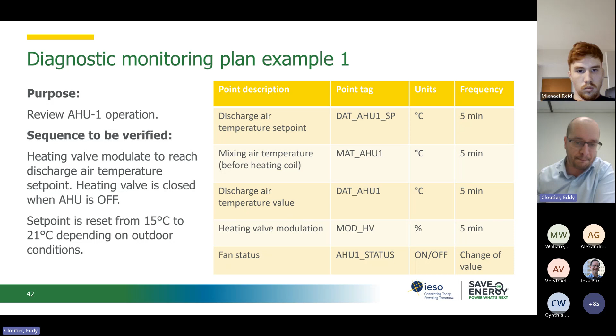Maybe I might add some information here. In the last column, you can see that in most cases we would probably propose a 5-minute interval for this monitoring plan. And for the last one, we set it to change of value. It's often an option that is proposed in the BAS system for trending data, which means in that case that we will save data only when there is a change. This is particularly useful for on-off points such as fans and pumps and so on.